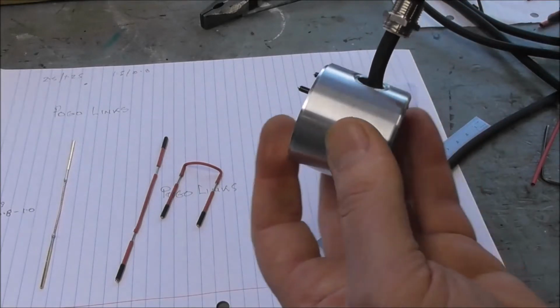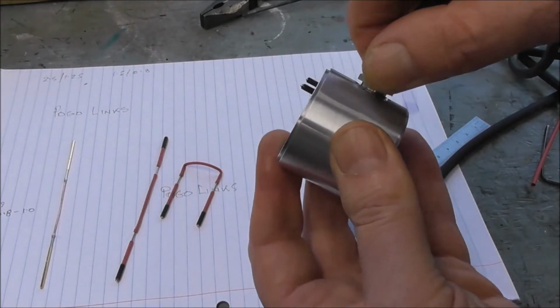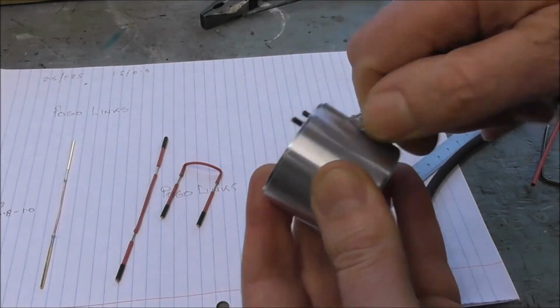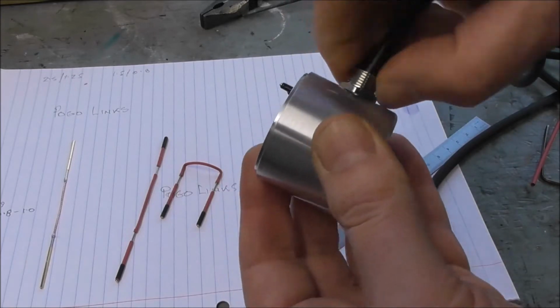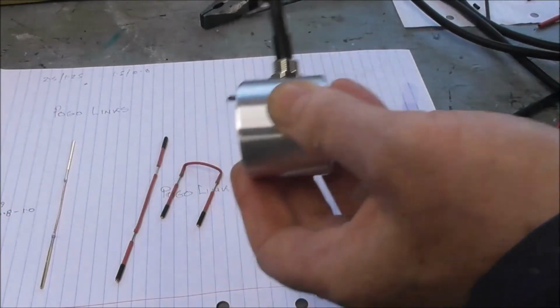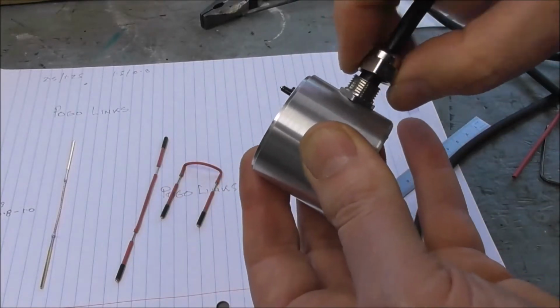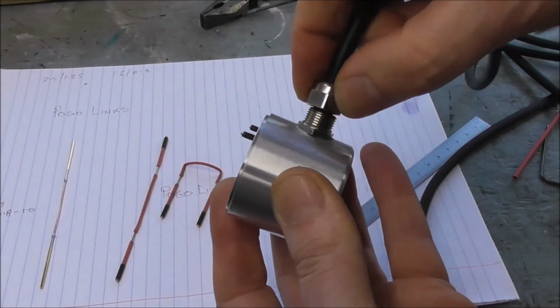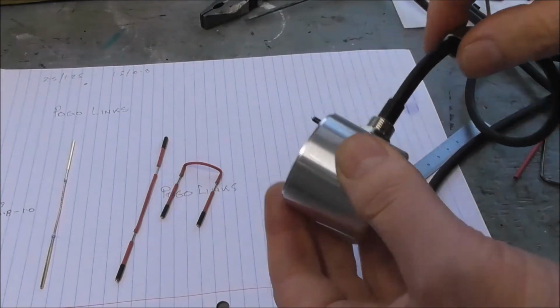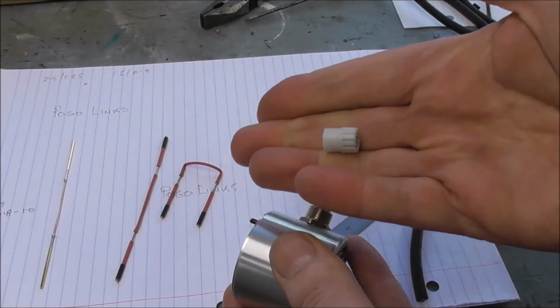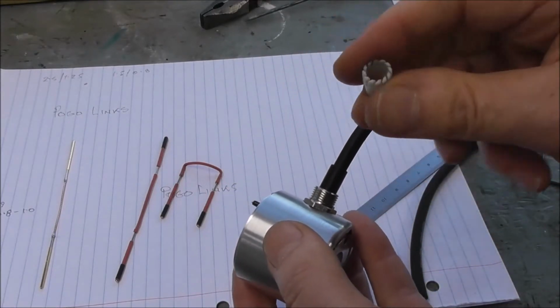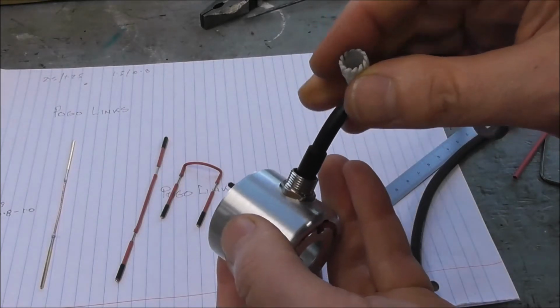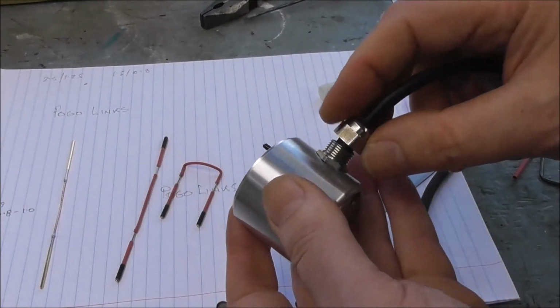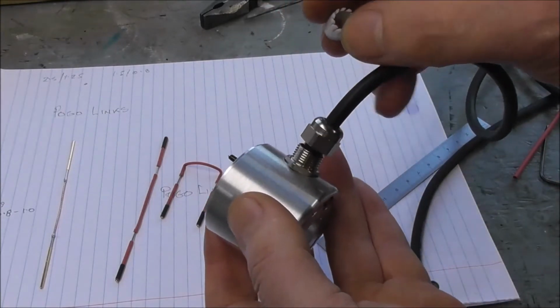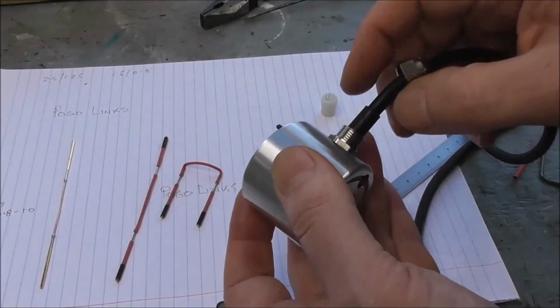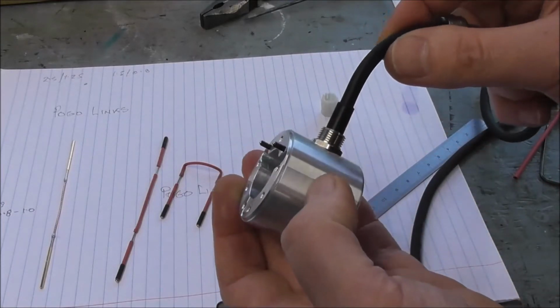Okay, so got that far. Now we're going to screw in the gland fitting. We're going to push in the little rubber protector. Finally screw on the gland nut and tighten it up. Just a note here, I've started leaving out the little plastic sleeve. That's designed to really grip on the cable, and it certainly does that well. The problem is that you tend to over tighten it, and the plastic little sleeve bites too deeply into the cable, and I think on balance it's better to have that out and just to have the rubber sleeve in there.